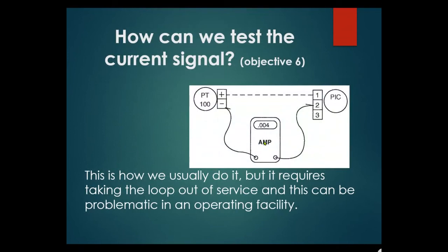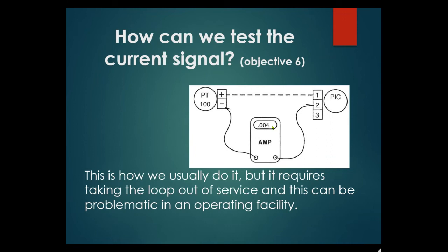Objective six — how to test the current signal: normally we put the ammeter in series, but that breaks the loop and can cause process problems. When doing calibrations we use this method because we cannot calibrate a live loop — it gives errors. In the field, if you're working on a loop, always tell operators you're going to work on it, put it in manual, then calibrate. Opening the loop requires taking it out of service, which can be problematic in an operating facility.